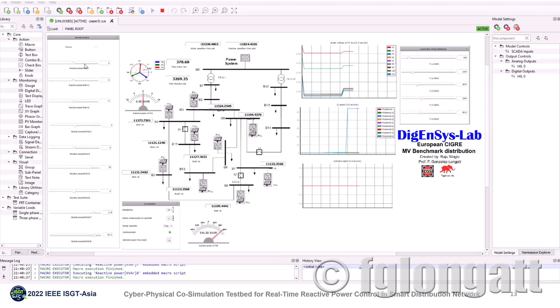If there is suddenly a cloud, you can see that the power production of the PV system can be reduced or increased depending on that. What is important is that if the voltages go beyond the limits, an activation signal will switch on the control algorithm, rescheduling the reactive power and sending a signal to the power converters in order to compensate the voltage variation.